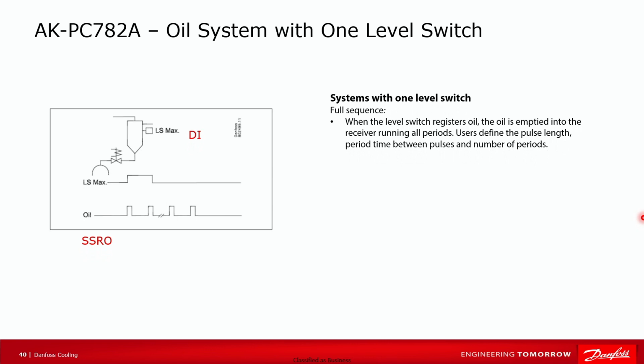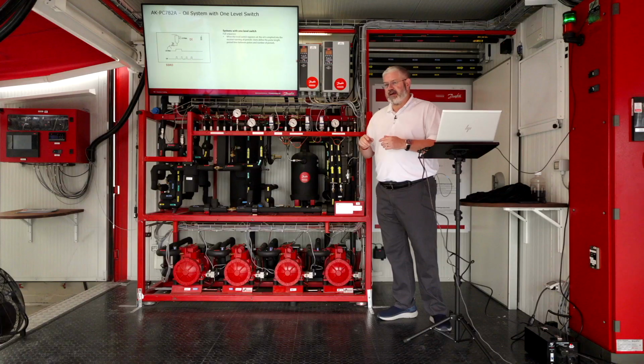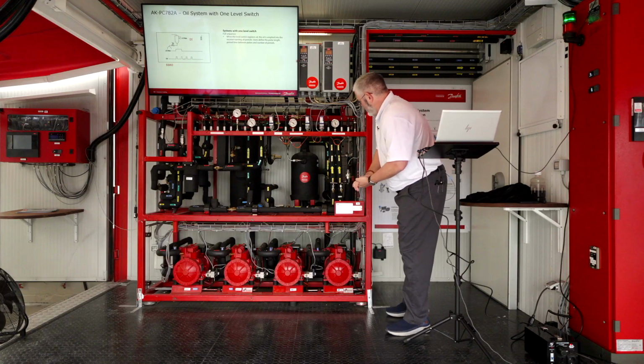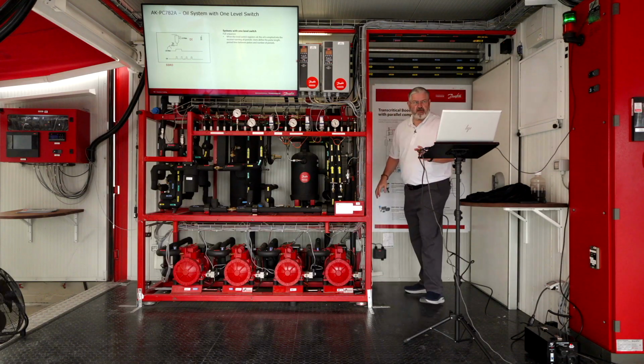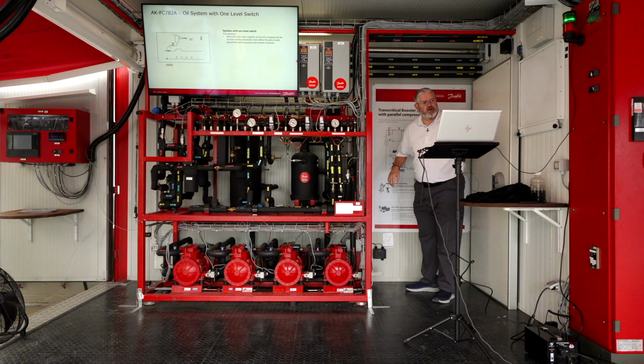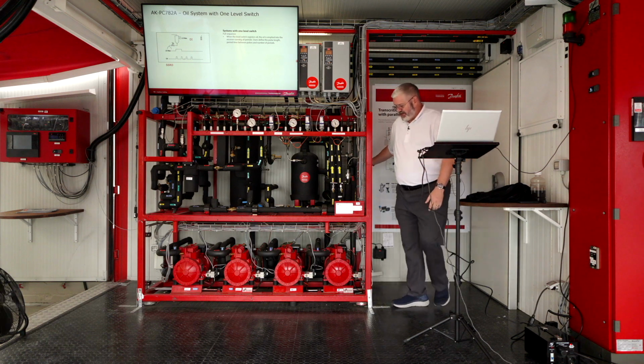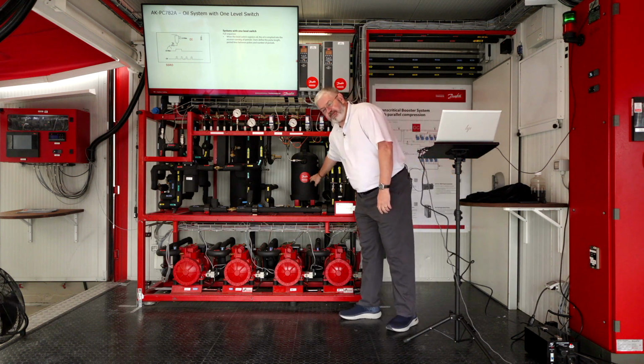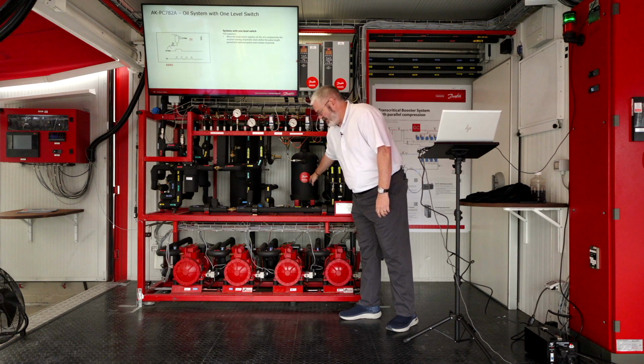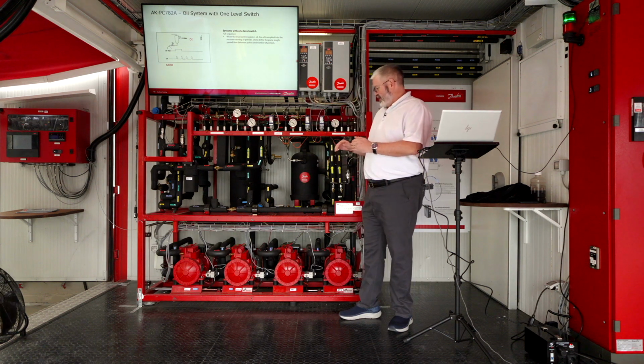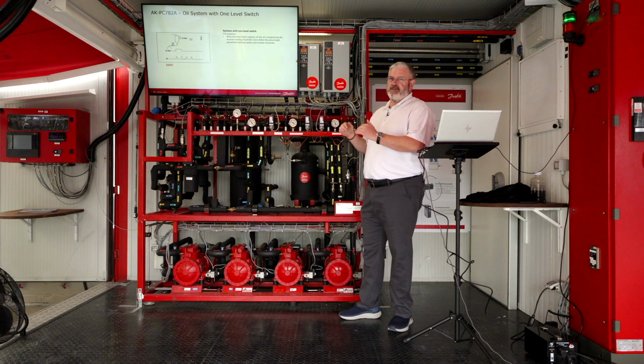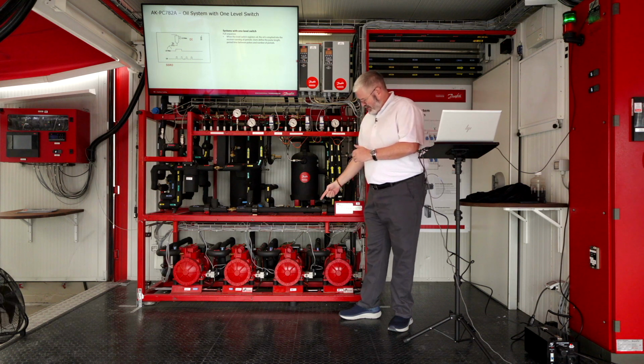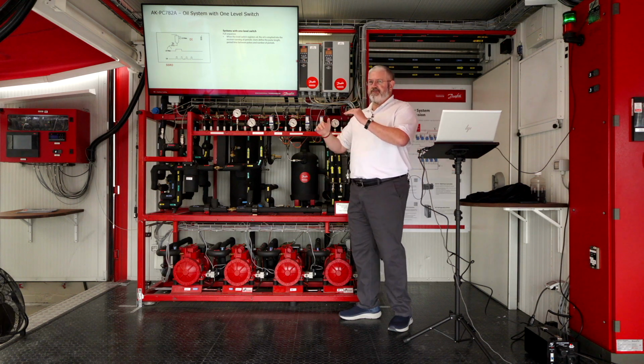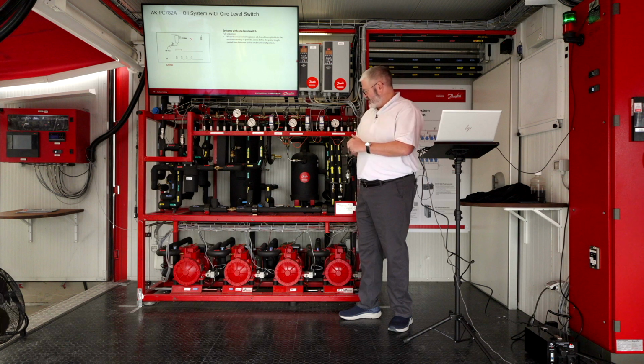So the first thing to note, before we start going through slides, if we can get the unit view. We've got an oil separator over here, like a large Pringles can that we saw earlier, and then that dumps into this fairly large oil reservoir. One thing to note on the reservoir: you don't want to have 1,300 pounds in the oil separator being what feeds the compressors, 900 pounds pressure drop across your oil solenoids.